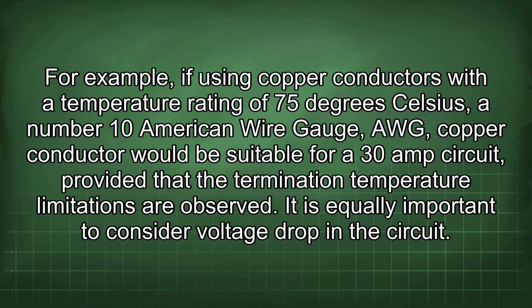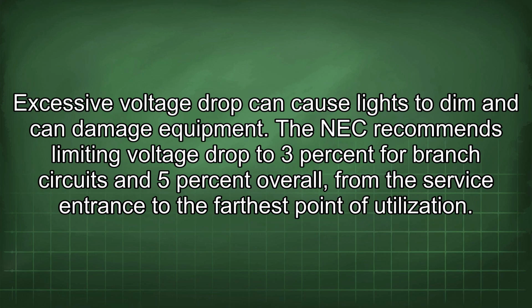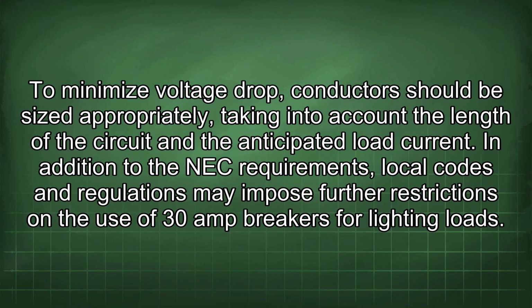It is equally important to consider voltage drop in the circuit. Excessive voltage drop can cause lights to dim and can damage equipment. The NEC recommends limiting voltage drop to 3% for branch circuits and 5% overall from the service entrance to the farthest point of utilization. To minimize voltage drop, a conductor should be sized appropriately, taking into account the length of the circuit and the anticipated load current.